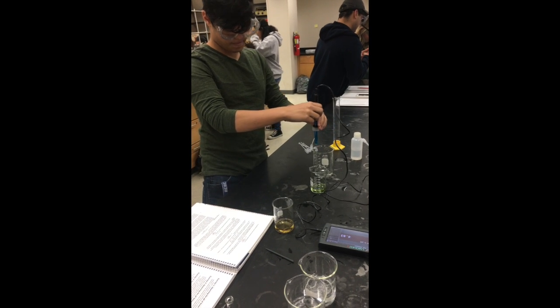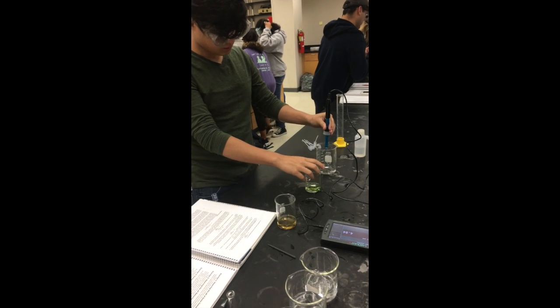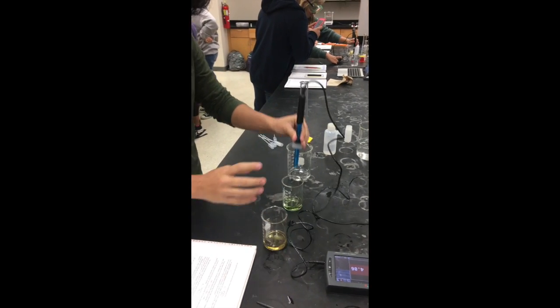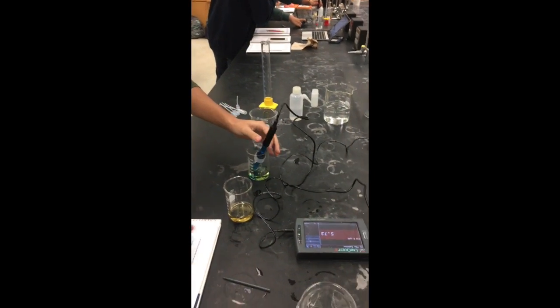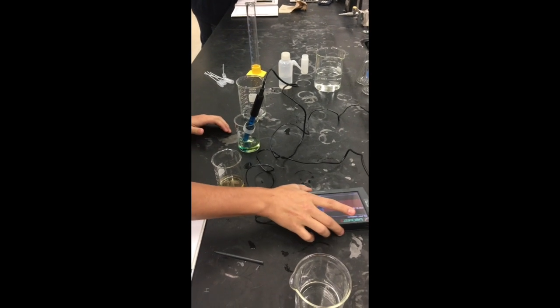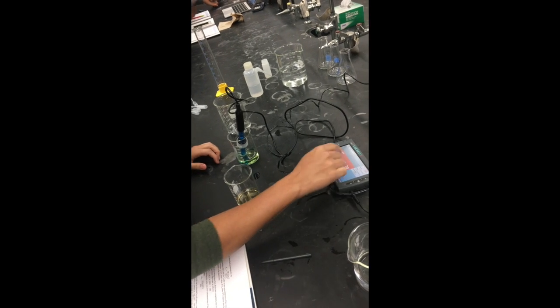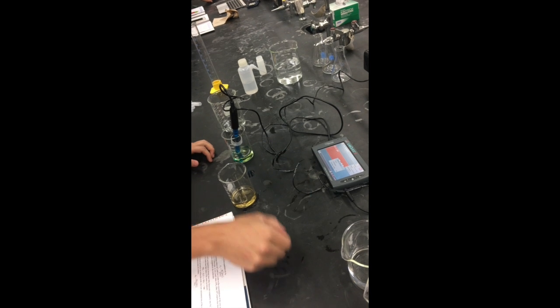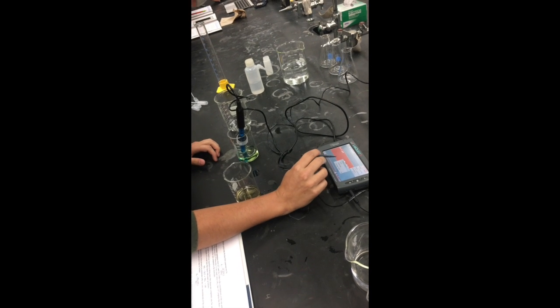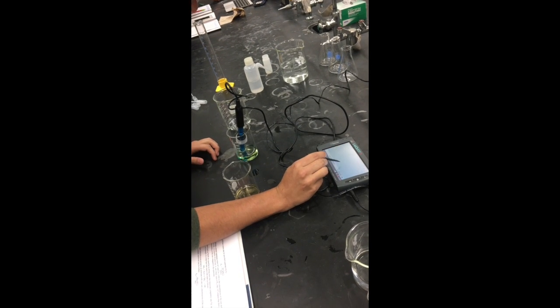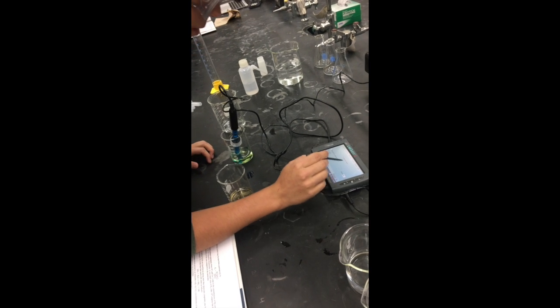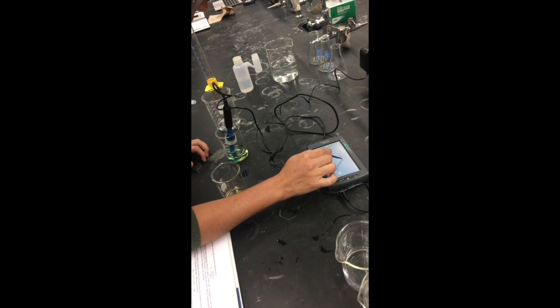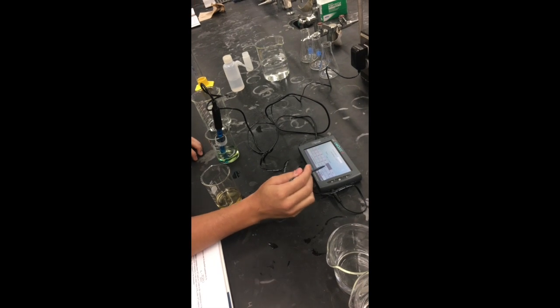Next, put the probe in one of the buffers. In this case, we are putting it in the pH 7 buffer. Allow about 30 seconds for the voltage to settle. On the LabQuest device, click Sensors, Calibrate, then enter the pH value of the buffer. In this case, it was 7. Rinse the probe, then repeat the steps for the pH 4 buffer.